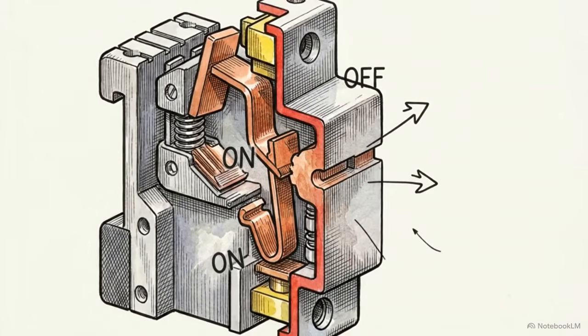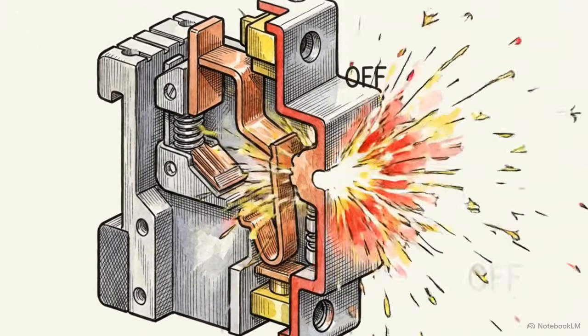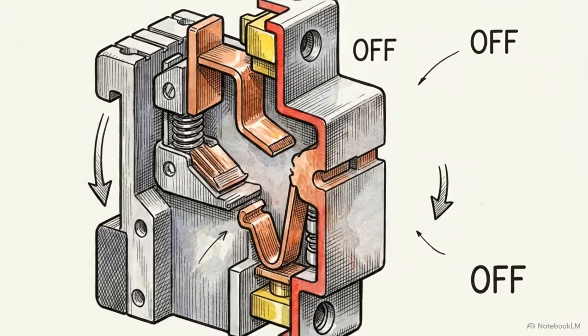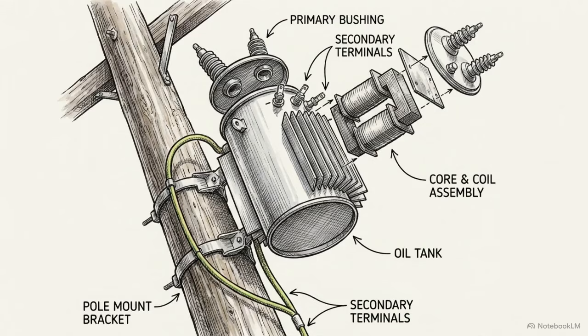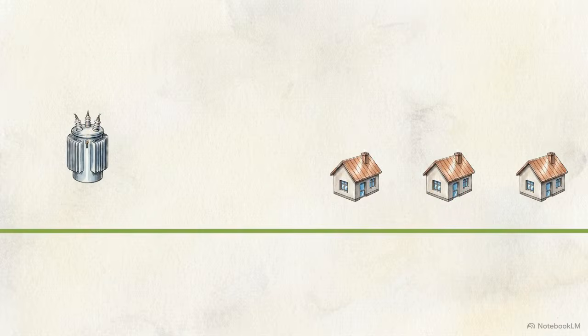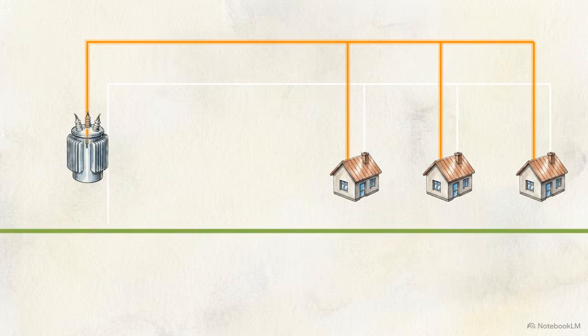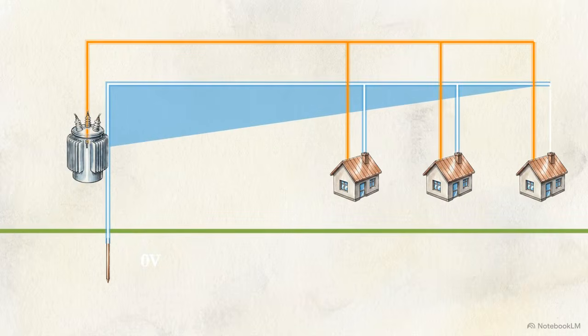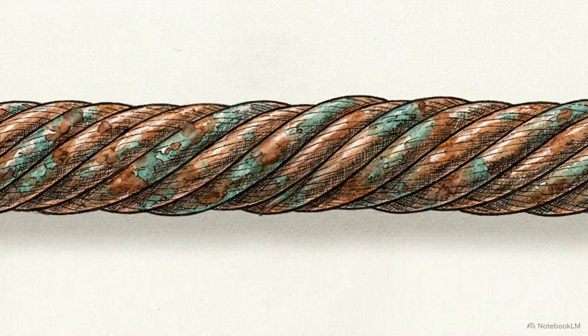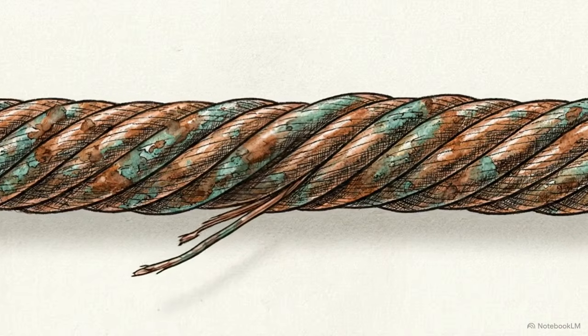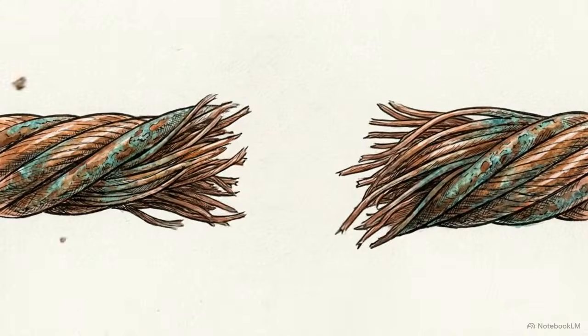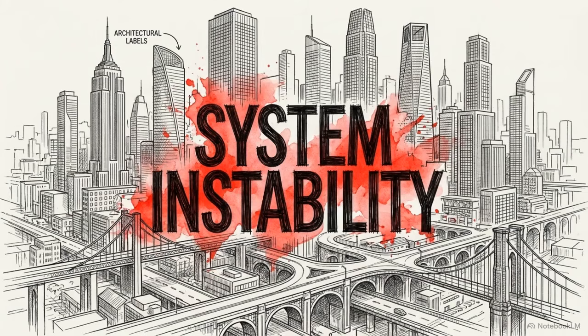Bonding and earthing do not stop a fault from happening. They deliberately redirect it, killing the circuit before it can kill a person. Moving back up the line to the power source, we encounter grounding. Unlike earthing, which deals with dead metal, grounding connects the live, current-carrying neutral wire to the earth, stabilizing phase voltages across the entire network. When this critical neutral connection snaps or heavily corrodes at the transformer, the entire system loses its 0-volt anchor. This triggers a disaster scenario known as a floating neutral.